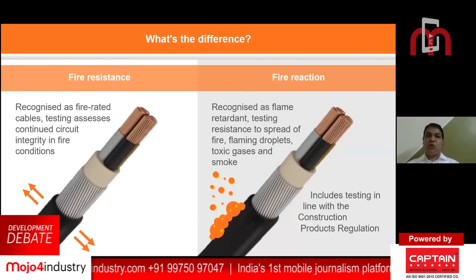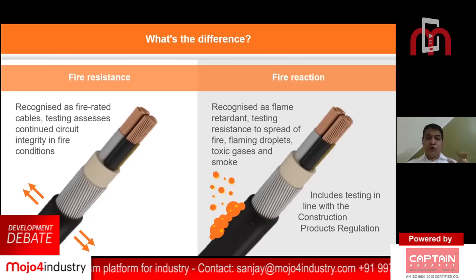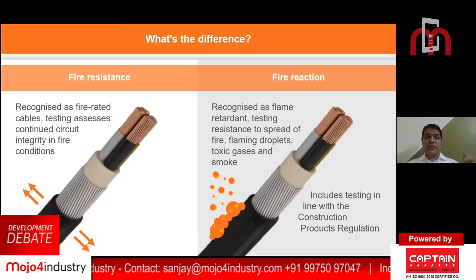Fire resistance cables are only for circuit integrity. At the end, when the fire is caught, it is to keep the firefighting system working, the emergency lights, the lifts, for evacuation purposes. For all this equipment to work, that is the reason it could be 1 hour or 2 hours—nowadays even a 120-minute test has come. So those circuits need a specific, separate power supply.